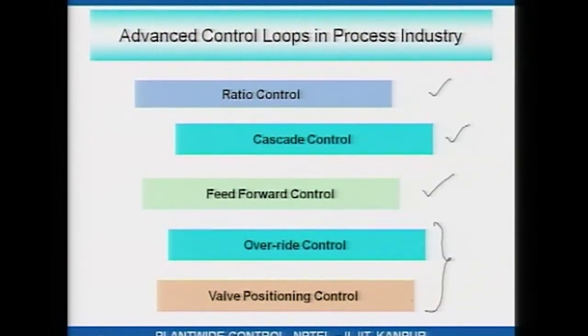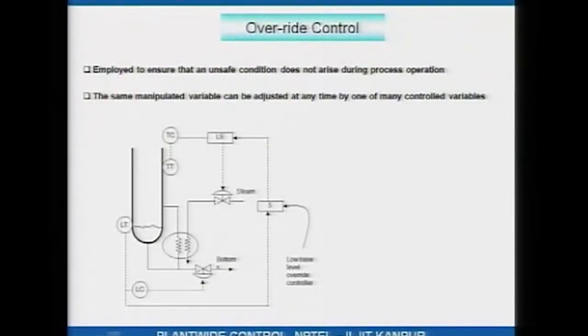We continue to discuss override control and valve positioning control. Override control, like the word indicates, is when an overriding circumstance occurs during process operation which can potentially result in a safety hazard. Override control ensures that the unsafe condition does not arise, and what override essentially means is the same manipulated variable is adjusted by different controllers.